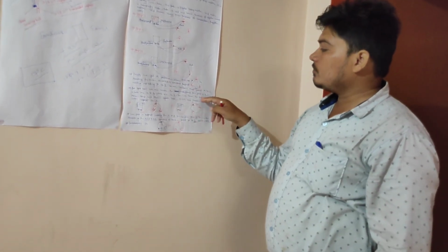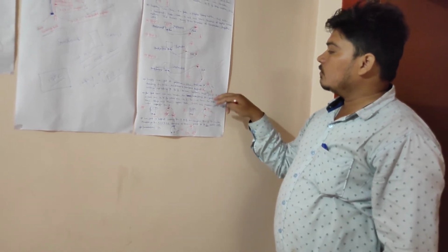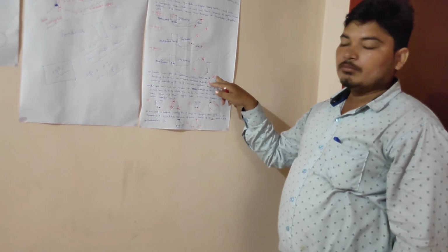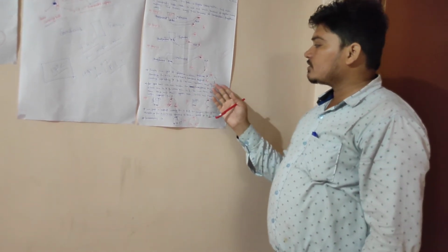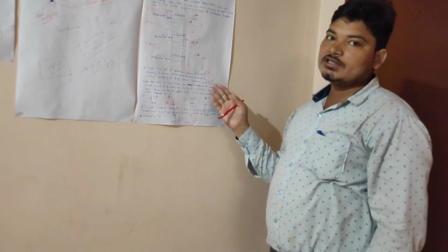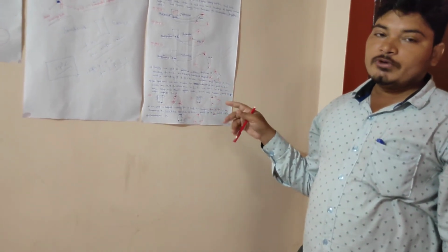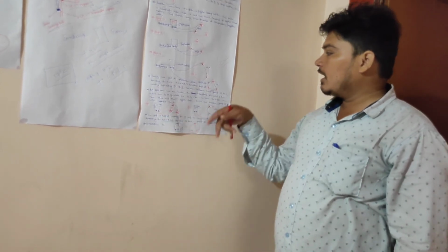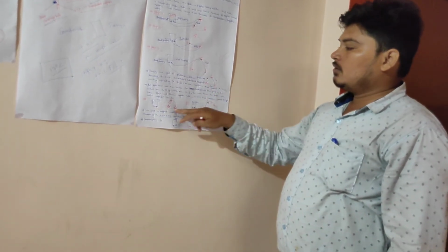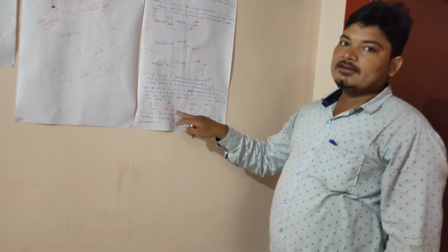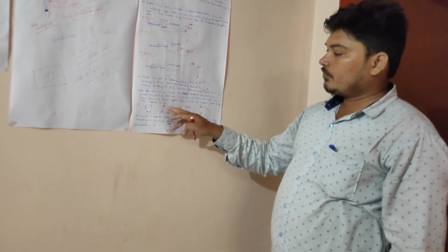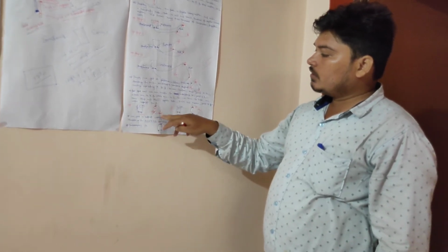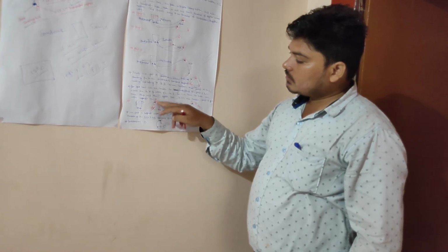In the last step, we know this point will be definitely common, point A, but we are unable to understand between B and C which one is the running and the starter. We have to take one more step, take a digital clamp meter and take a reading about these two points B and C with respect to A.